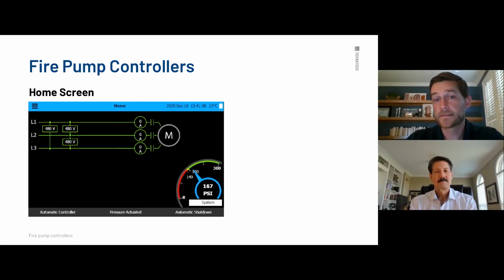until it satisfies the pressure, which I believe this one is probably set at 160. The needle is kind of blocking that, but you can see the green transition there. From 140 to 160 there's going to be a little bit of a yellow line, that's in between your cut in and cut out, and then it's green from your cut out point until the end of the meter there at 300. So this one being automatic shutdown enabled, once the system pressure gets back up above, you'll see a timer start going for 10 minutes, or whatever you have that automatic shutdown set for, and after 10 minutes the timer has expired, then the pump will shut off automatically.